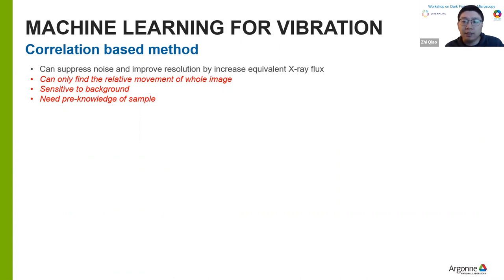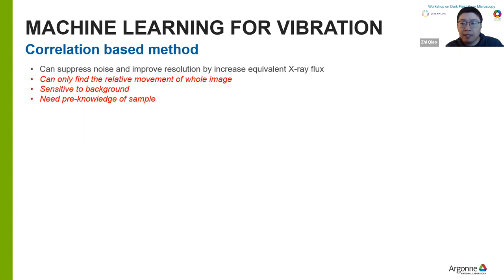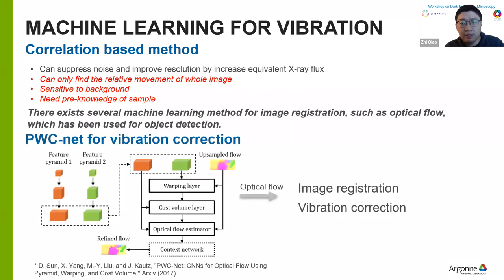The cross-correlation-based method can effectively mitigate image blurring due to mechanical instability. However, there are some shortcomings. First, the cross-correlation method can only get the relative displacements of the whole sample, so local instability is ignored. Also, the cross-correlation method is sensitive to the image background — if the illumination beam fluctuates too much, the method will fail to find the right displacements. Another disadvantage is that it requires pre-knowledge of the sample, which is very difficult for dark field imaging. There are several machine learning-based methods for image registration that may also be applicable to the dark field microscope.